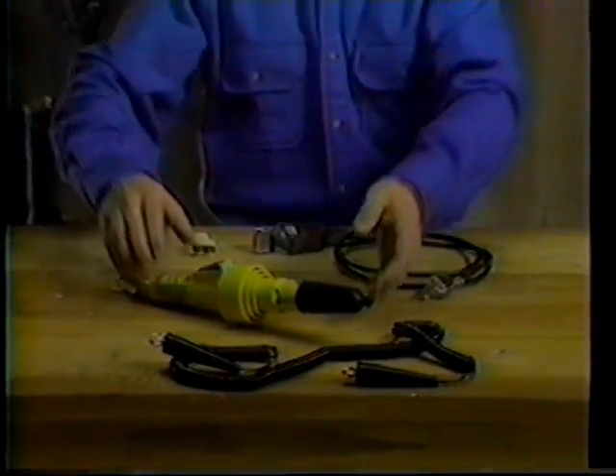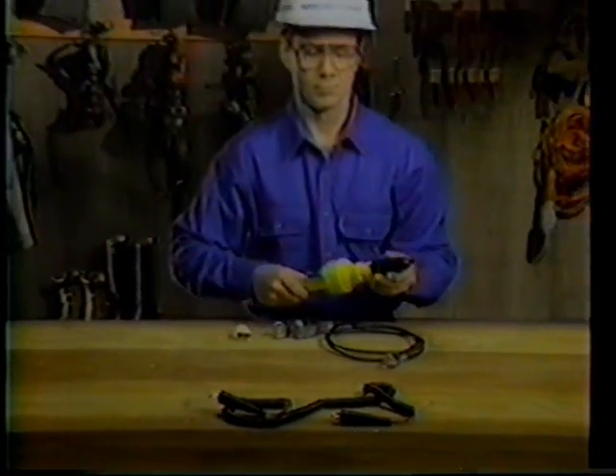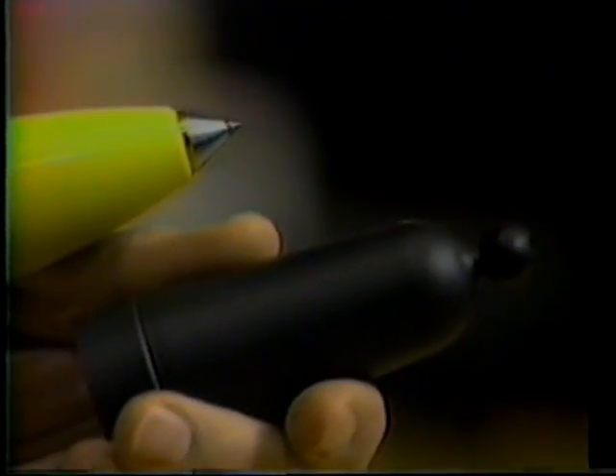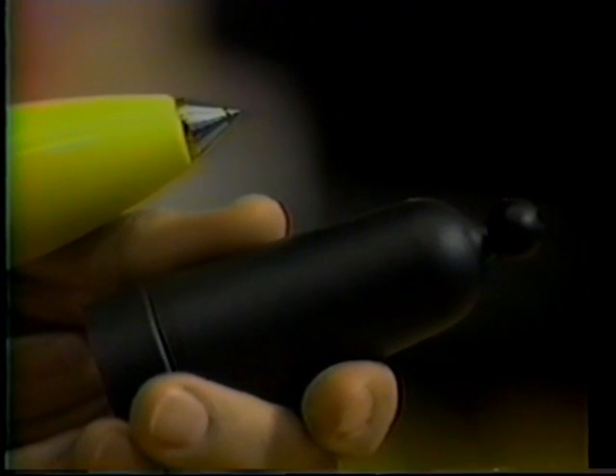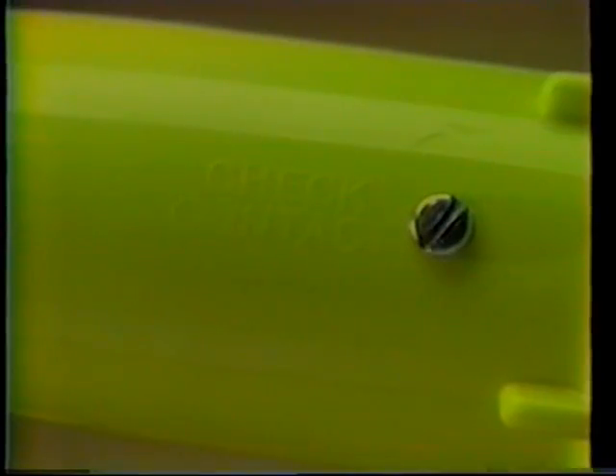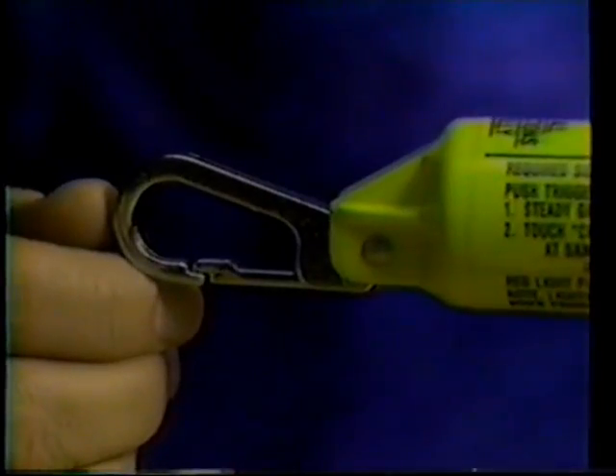The 188A test set is a yellow plastic two-piece unit that weighs approximately 1 pound. The front housing contains a carbide probe tip protected by a conductive cap. It also contains 2 warning lights, one red and one green. The right side of the 188A houses a ground post, and the left a check contact. The rear housing contains a belt clip and an operating switch.